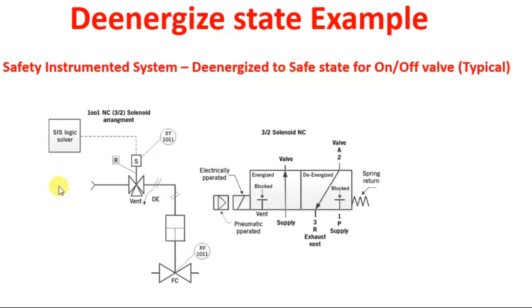Based on the process conditions — by detecting pressure high, temperature high, or flow high from the SIS sensors in the respective vessels and areas — the logic solver performs the mathematical computation inside and then sends an output through the relevant output modules in the logic solver. The logic solver output goes to the solenoid valve, which is a 3-by-2 solenoid valve as mentioned in the earlier slide.